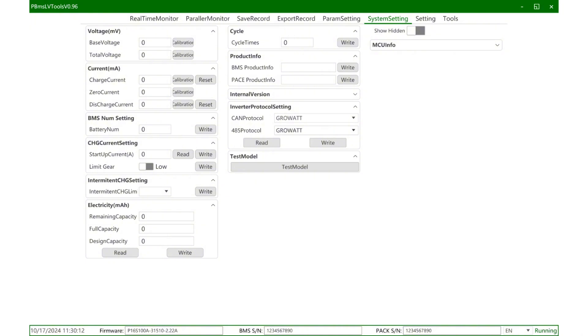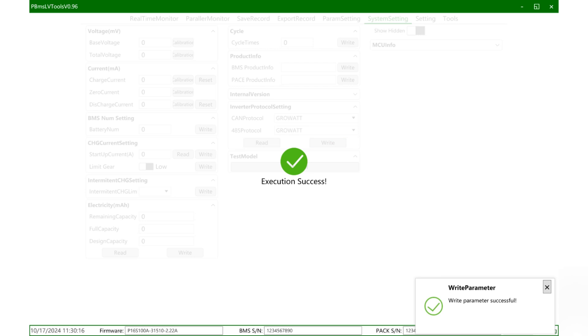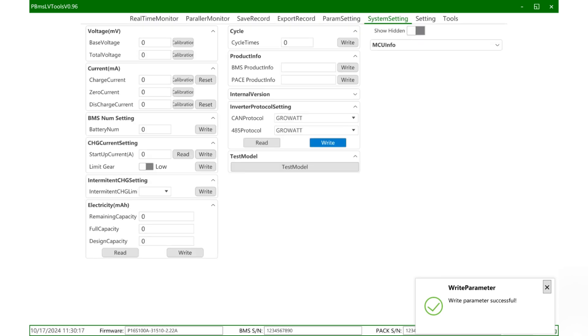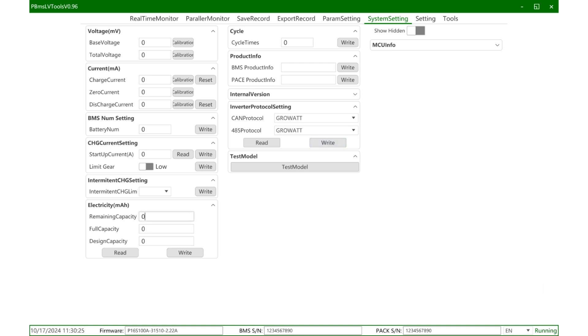If you want to switch to another inverter protocol, you can click here. For example, if you need to match the Growatt protocol, you can click the Growth protocol and then click write. At this time, it will show that the operation is successful. Read and write again. If the corresponding protocol is displayed, it means that the switch has been successful. Similarly, the 485 protocol switch is similar to the above operation.